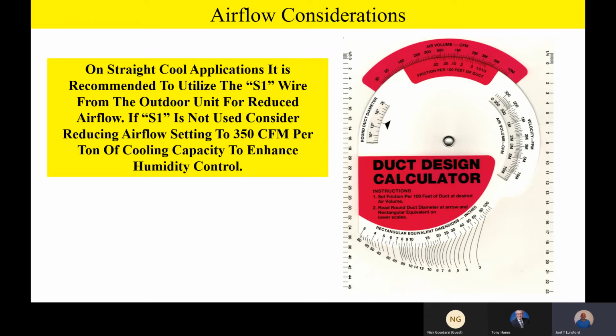However, if S1 is not used, please consider reducing the airflow to 350 CFM per ton of cooling capacity to enhance humidity control if you're in a humid environment. So it's perfectly fine to reduce your airflow down to 350. We're going to design our ductwork for 400 CFM per ton. But if you've got a humid environment, there are some things you can do by reducing your airflow down to 350. I've already talked to some factory engineers. It's okay to do that.